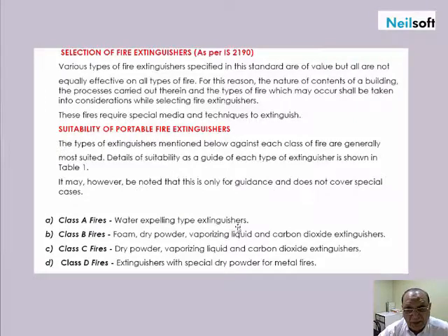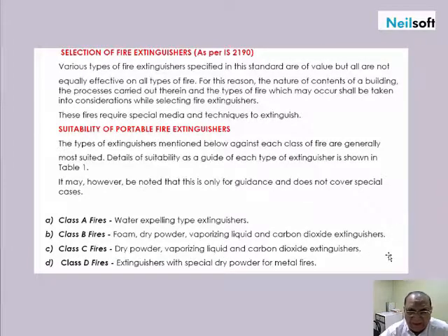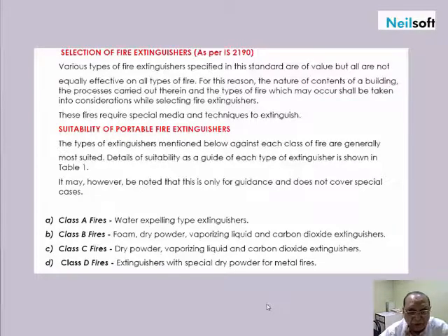To summarize the extinguisher types by fire class: Class B fires use foam, dry powder, or vaporizing liquid extinguishers. Class C fires use dry powder, carbon dioxide, or vaporizing liquids. These will be discussed and explained further as needed. This concludes Part 3 of our training.